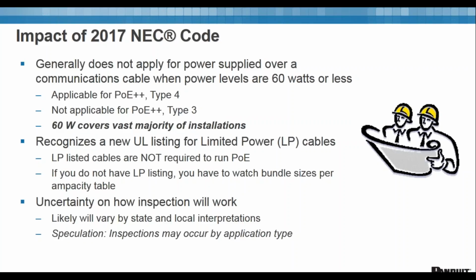What it means is that, with Type 3, that's your 60 watt at the power source, and that covers the vast majority of installations. Simple way to think of it is everything you got running for PoE now, that's 60 watts or less, because nothing else exists right now. So all that stuff you got running today, this does not impact, does not cover. However, for those highest power standards, it may cover, or it will cover. Recognizes a new UL listing for limited power or LP cables. To be clear about it, LP cables are not required to run PoE. However, if you do not have an LP listing, you will have to watch your bundle sizes per an ampacity table.